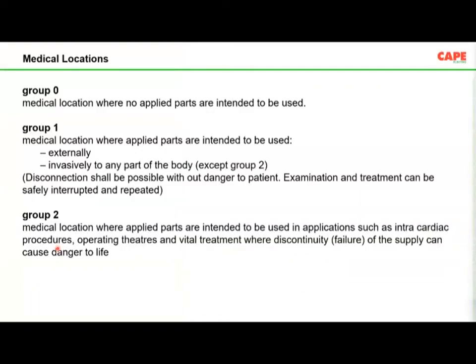Now, medical locations are classified into group 0, group 1 and group 2 medical locations. So group 0 medical locations are where medical electrical equipment can be brought into contact with the patient or needs to be touched by the patient, but basically the applied parts are not intended to be used. Medical locations where no applied parts are intended to be used are called group 0 locations, but it doesn't mean that the person is not allowed to touch the electrical appliance. Yes, of course, that is allowed.